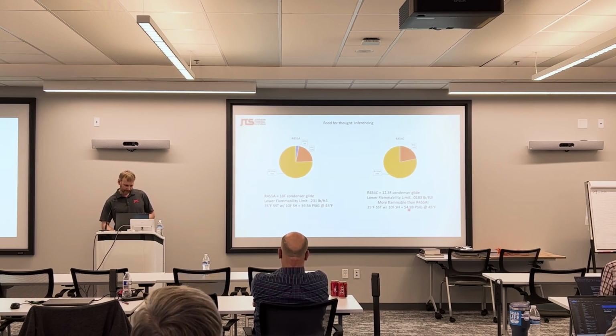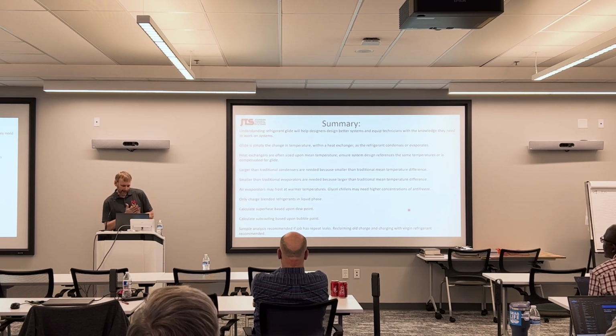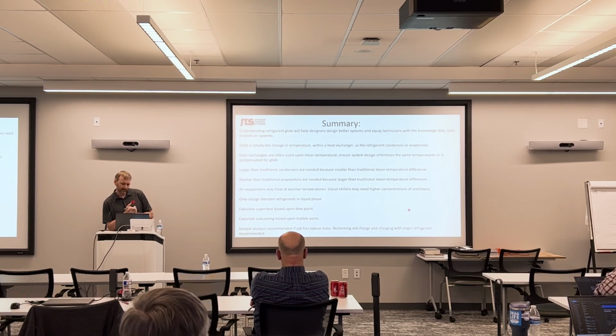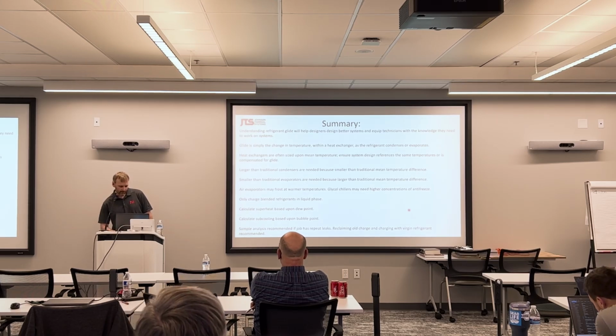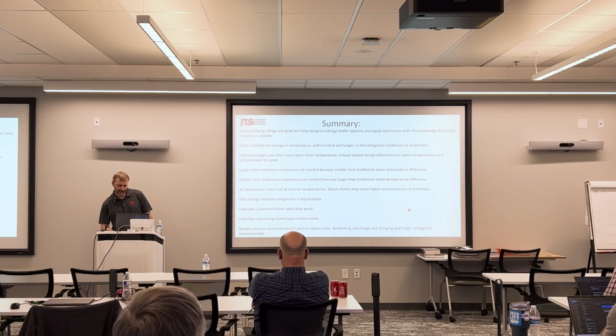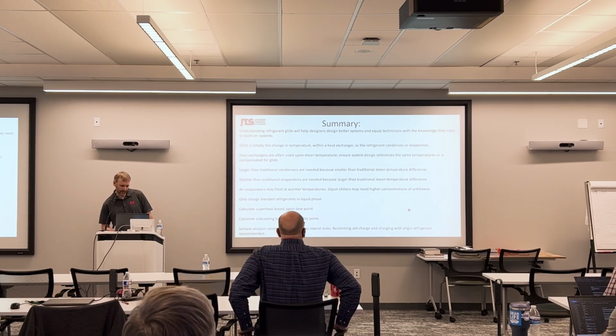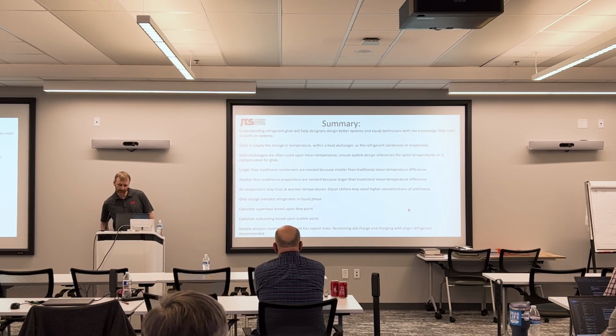So, in summary, understanding refrigerant glide will help designers design better systems and equip technicians with the knowledge they need to work on the system. Glide is simply the change in temperature within the heat exchanger as the refrigerant condenses or evaporates. Heat exchangers are often sized on mean temperature difference. Ensure that the system design references the same temperature or is compensated for glide. Larger than traditional condensers are needed because of smaller than traditional temperature difference. Smaller than traditional evaporators are needed because of larger than traditional mean temperature differences.